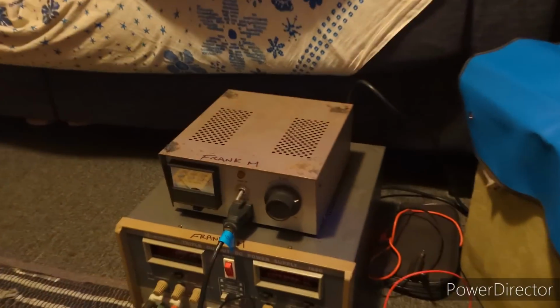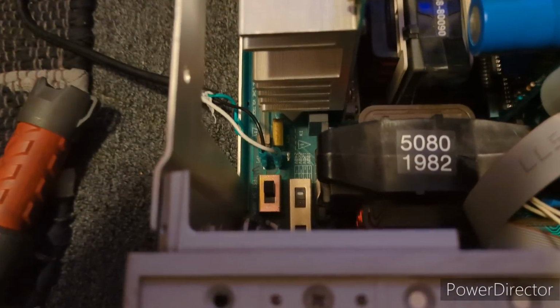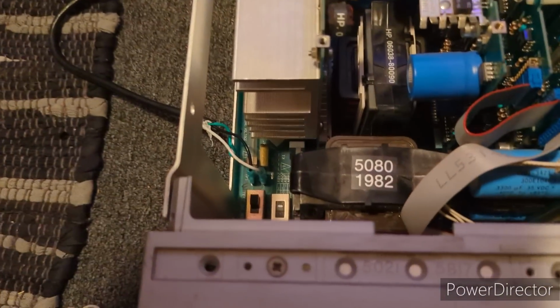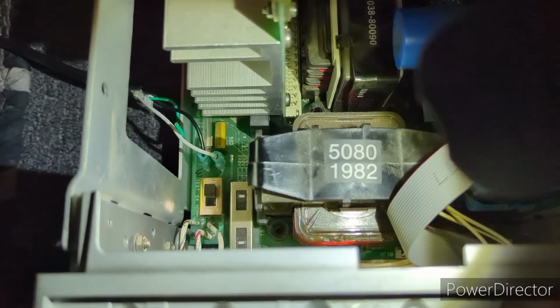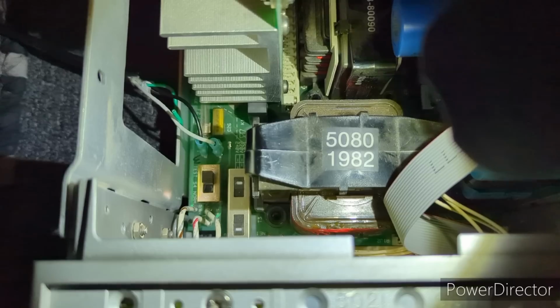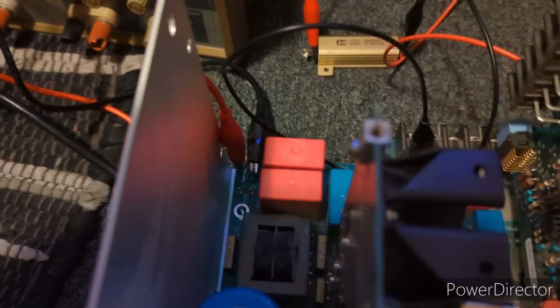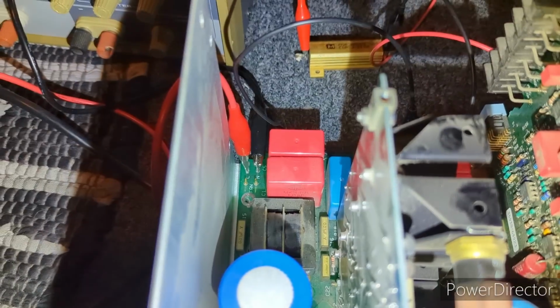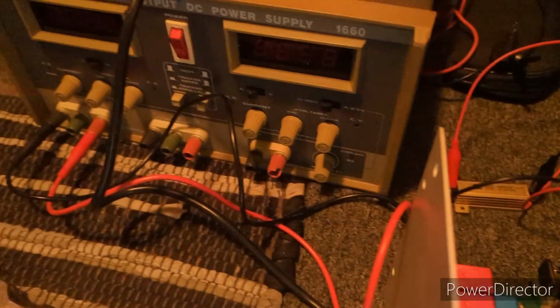So got the isolation transformer. So that is connected to test point 1 and 2, and hold on, let's see. Yep, and so we've got that switch there in test mode, and then we've got our power supply hooked up to, well, I don't have the receptacle connected, but that's where the line and neutral connections go, right there. All right, so that's where our DC power supply is.